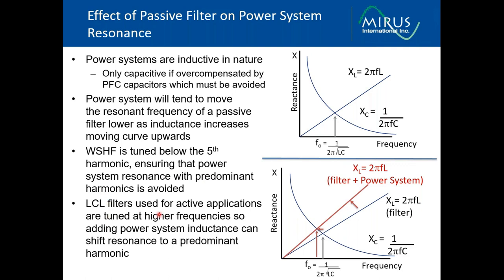But LCL filters used on active solutions are tuned much higher. So if they're tuned out here and connected to a power system, depending on that power system inductance, it'll shift that resonance frequency, and it could shift it to a predominant harmonic on the system, creating resonance.